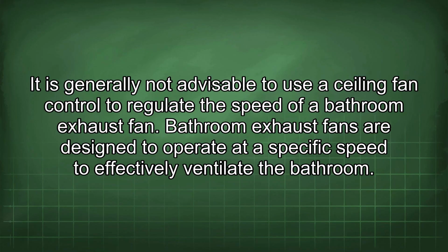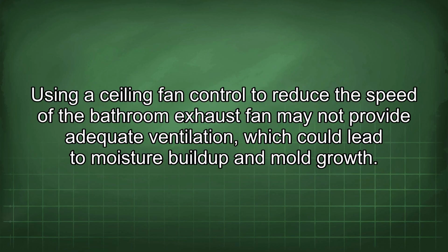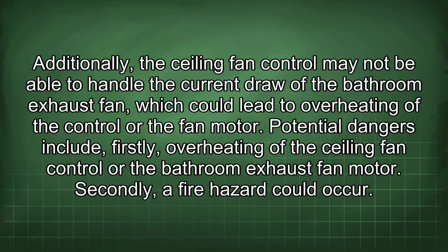It is generally not advisable to use a ceiling fan control to regulate the speed of a bathroom exhaust fan. Bathroom exhaust fans are designed to operate at a specific speed to effectively ventilate the bathroom. Using a ceiling fan control to reduce the speed of the bathroom exhaust fan may not provide adequate ventilation, which could lead to moisture buildup and mold growth. Additionally, the ceiling fan control may not be able to handle the current draw of the bathroom exhaust fan, which could lead to overheating of the control or the fan motor.